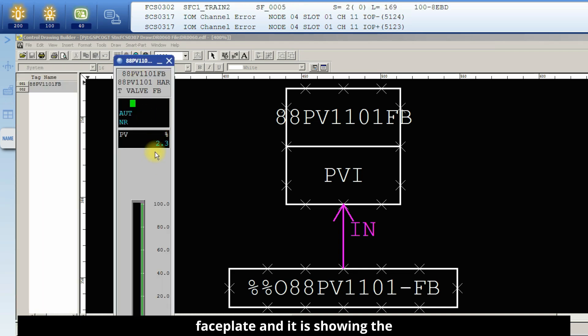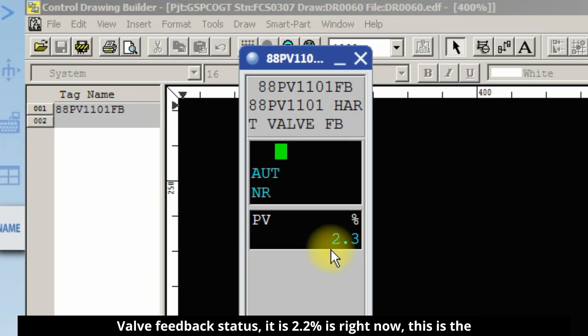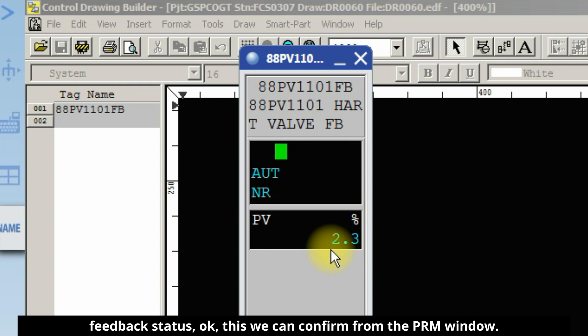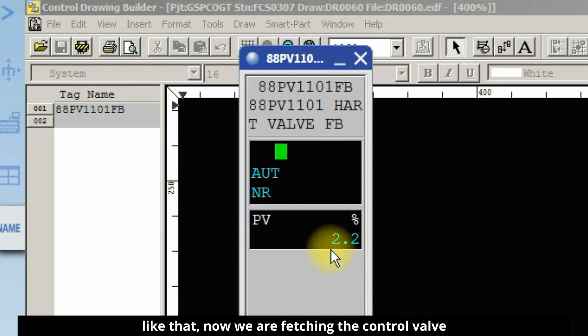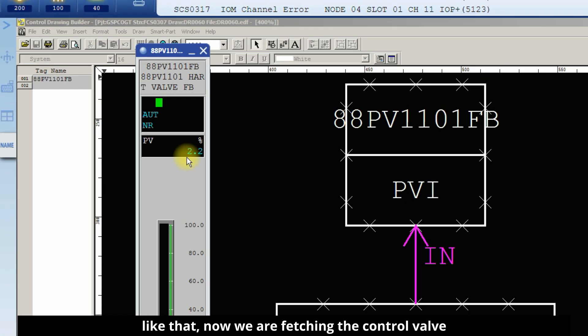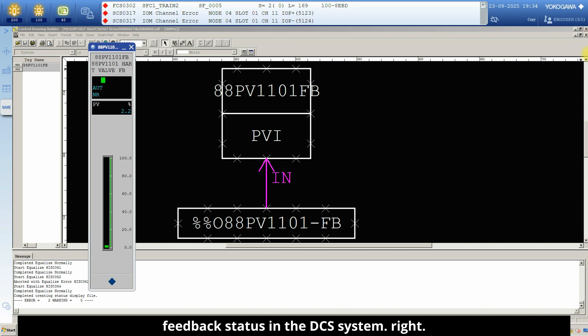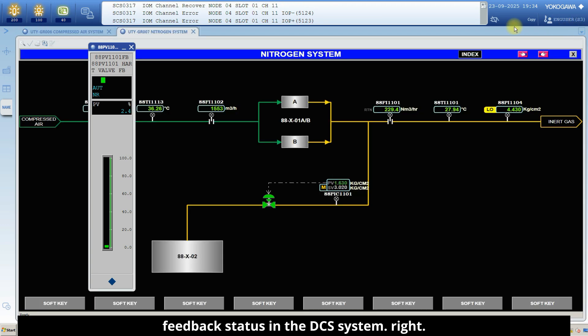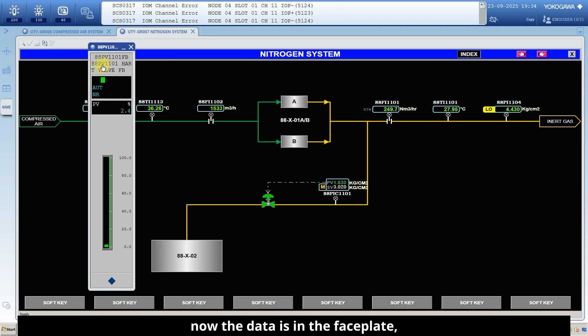This is the faceplate and it is showing valve feedback status. It is 2.2 percentage right now. This is the actual percentage, the valve feedback status. This we confirm from the PRM window. It may vary, no problem, 2.2, 2.3, 2.1 like that. Now we are fetching the control valve feedback status in the DCS system. Now the data is in the faceplate.